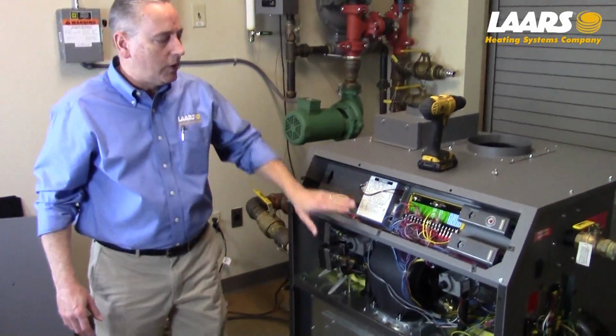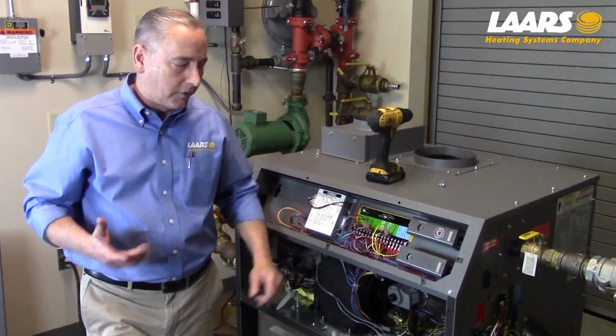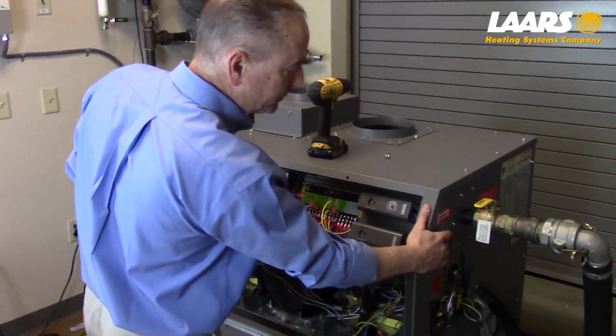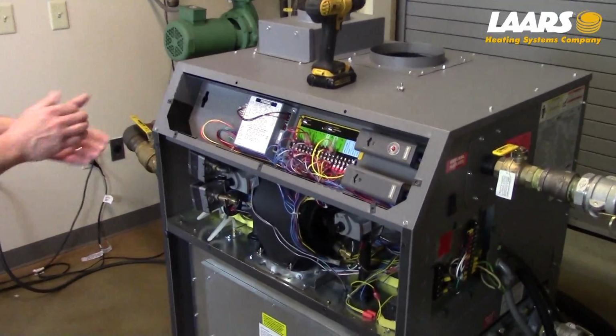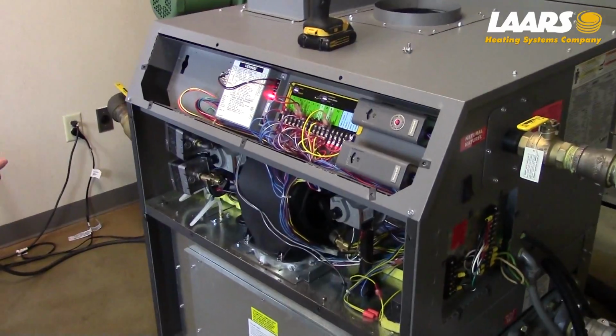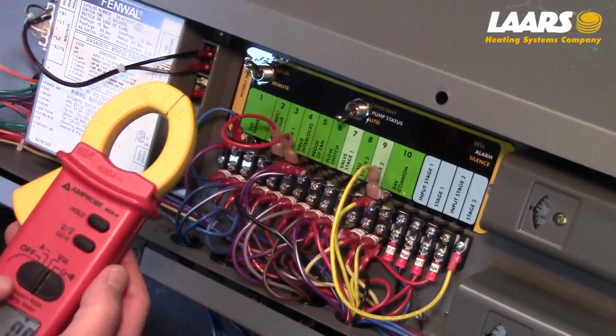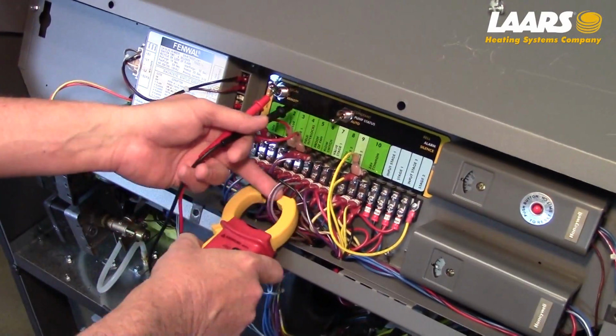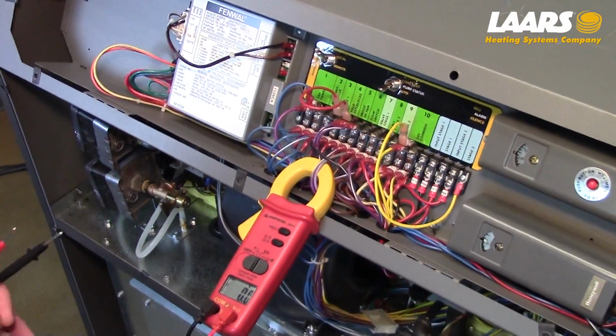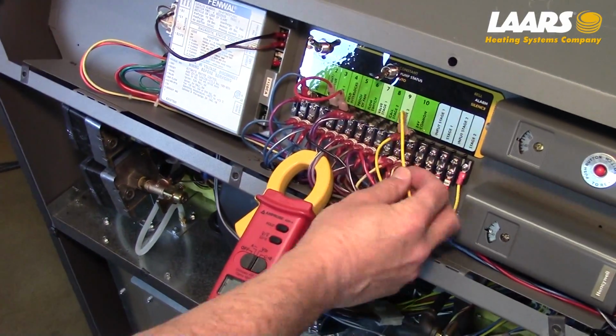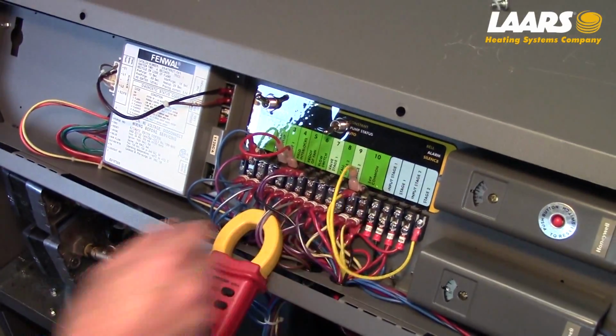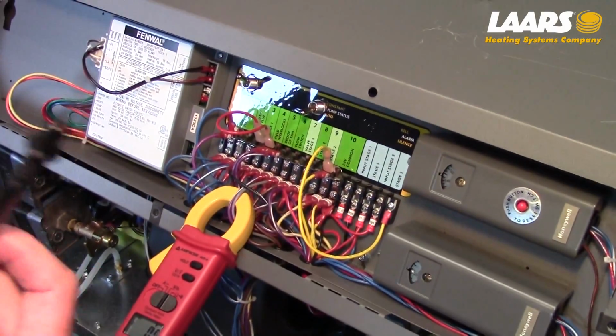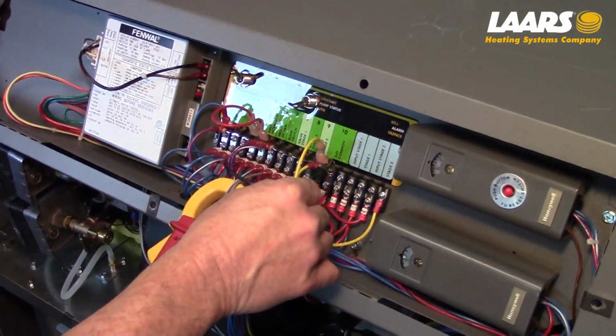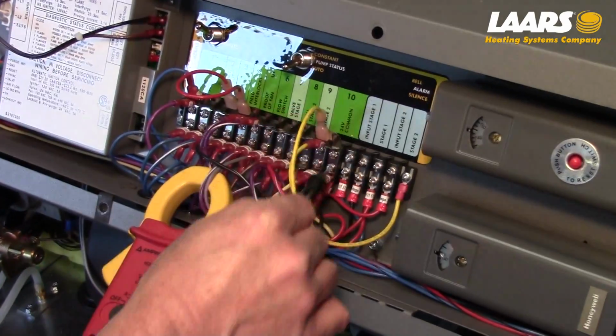Okay, we're going to troubleshoot the safety circuit. I'm going to start by powering up the boiler, and then we're going to walk through the terminal strip. Alright, so I've got my voltmeter hooked up to voltage. I'm just going to clamp it here to hold it in position so you can see it. I want to mention to you, all of our yellow wires here are 24 volt common. So I'm going to start with 1 voltmeter and put it on 24 volt common here on terminal 10.